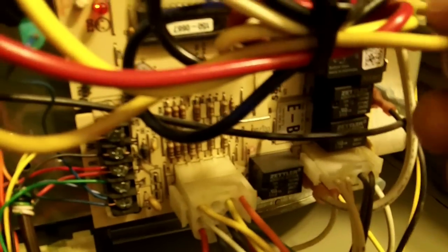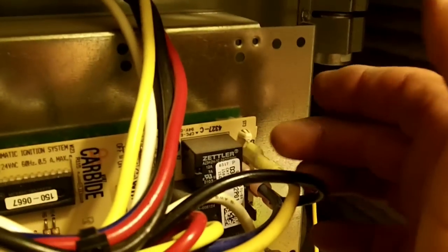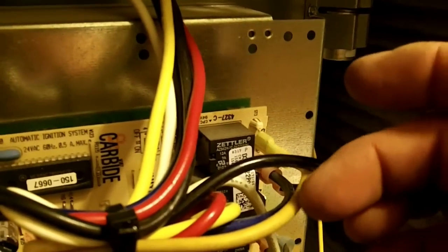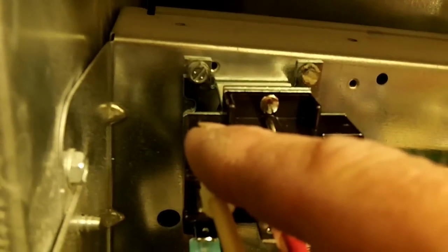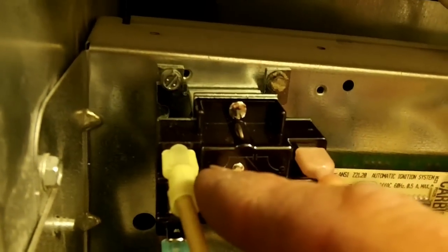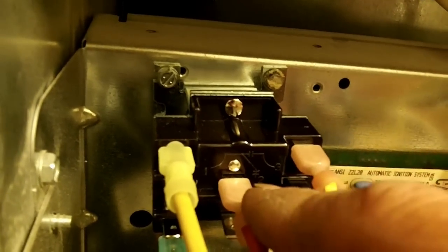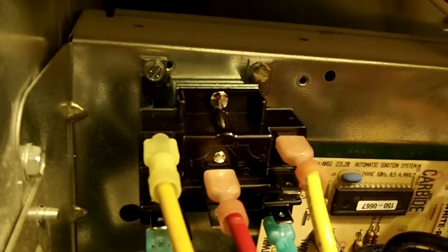And then I use brown for Y2. So what I'm doing is—let me start over. When the thermostat gets the signal from green, it's going to hit the G terminal and turn the relay on, go to the cooling terminal, then feed over to the common part of the relay. If it's in Y1, it's going to go from here to the low speed and bring the low speed fan on.